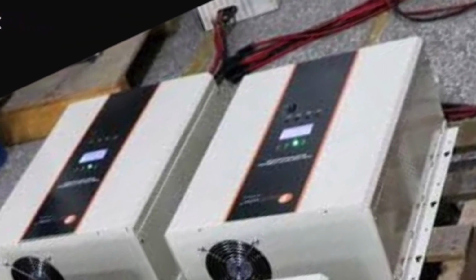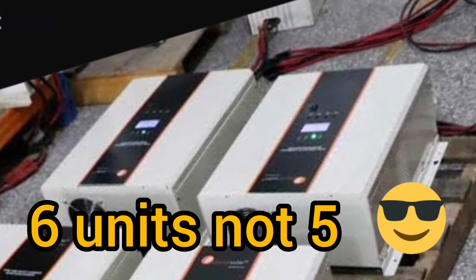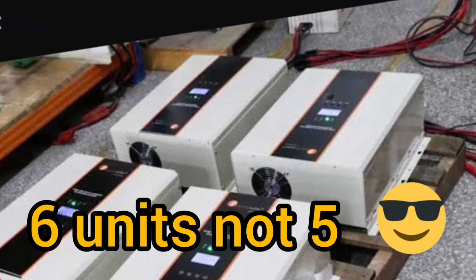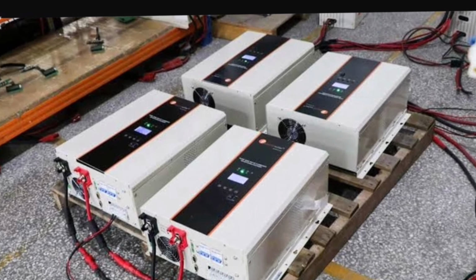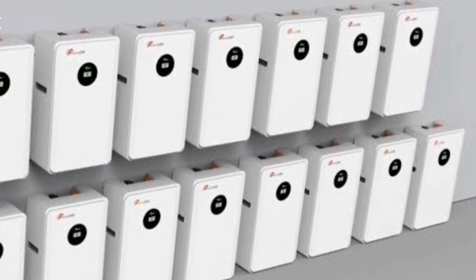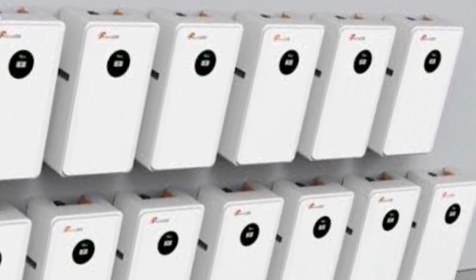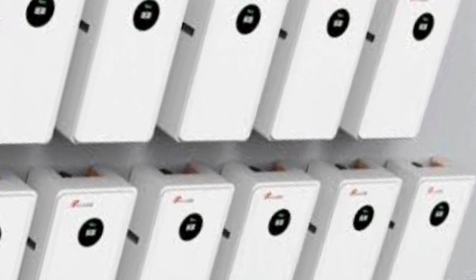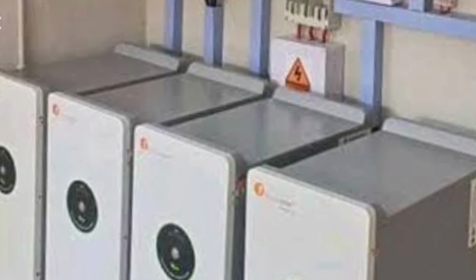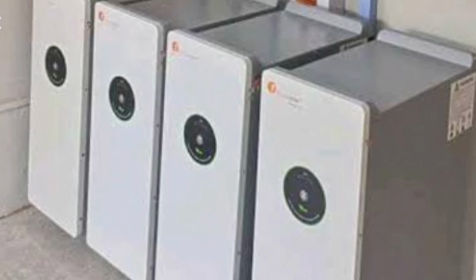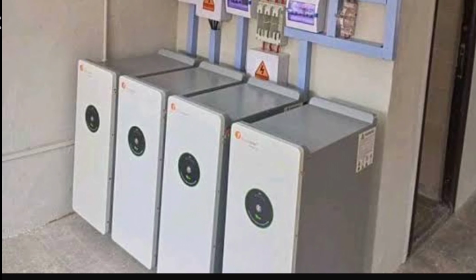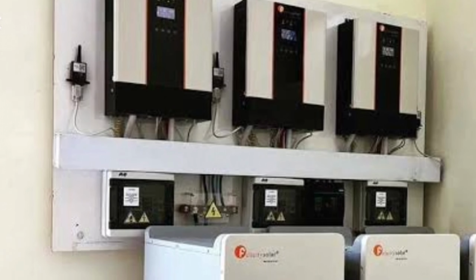One other interesting thing is that we can stack these batteries up, in units of 5 - meaning we can connect them as one. So if I have 5 units of the 5 kilowatt hour lithium iron phosphate battery, I can join them to make one 25 kilowatt hour battery. I can do the same with the 10 kilowatt hour ones to get a maximum of 50 kilowatt hour, and with the 15 kilowatt hour ones to get 75 kilowatt hour. There's also a 25 kilowatt hour unit, and if you stack 5 of those, you get 125 kilowatt hour.